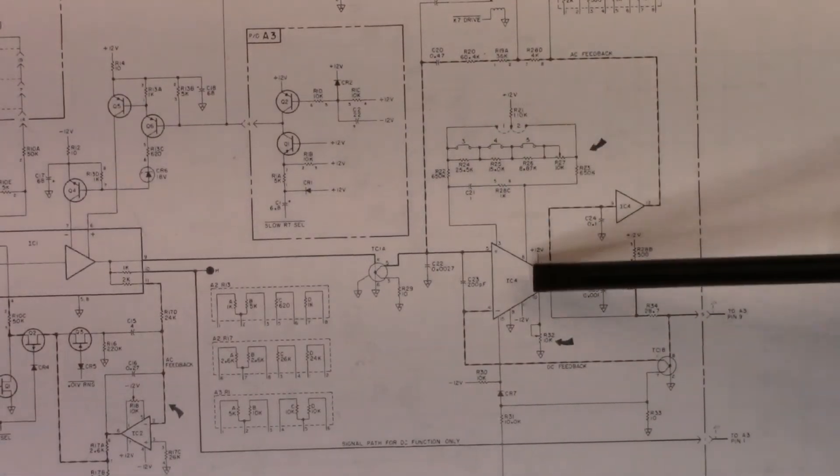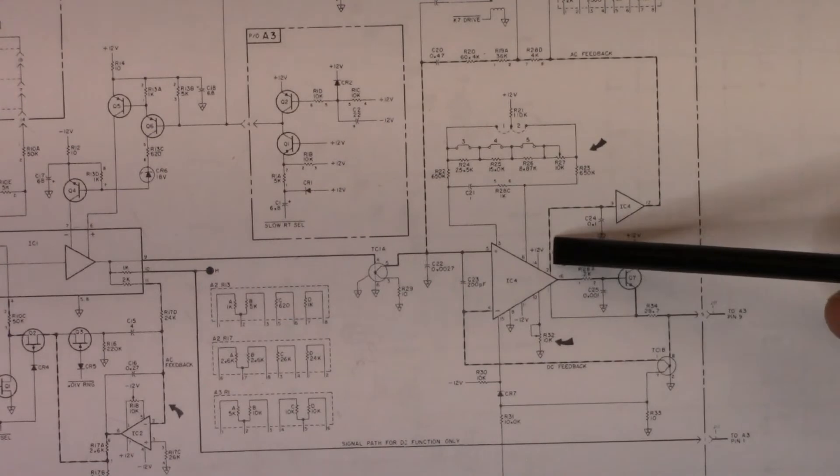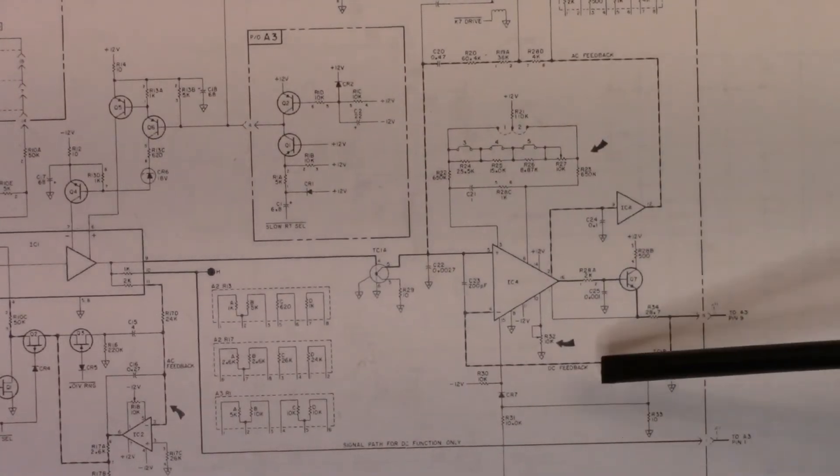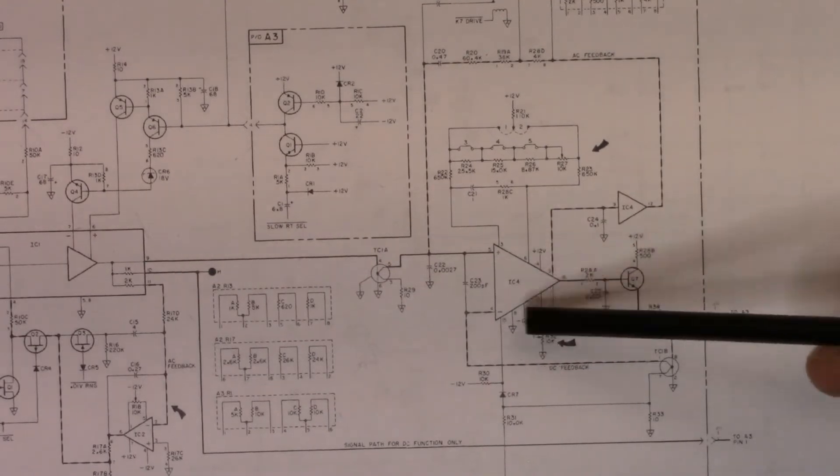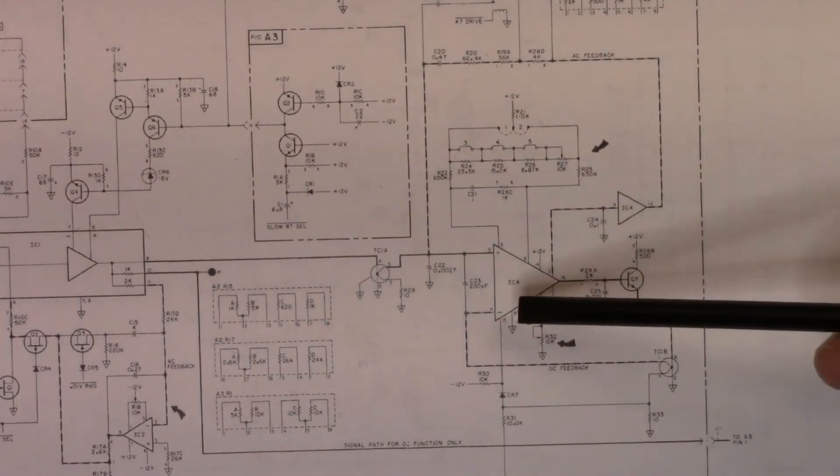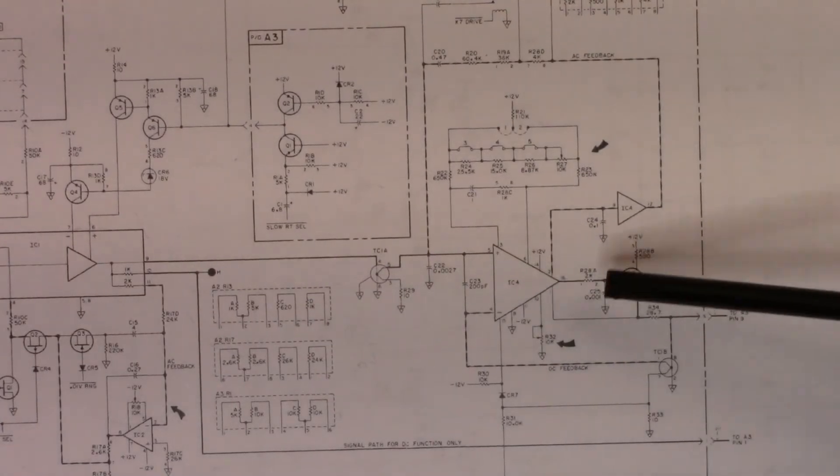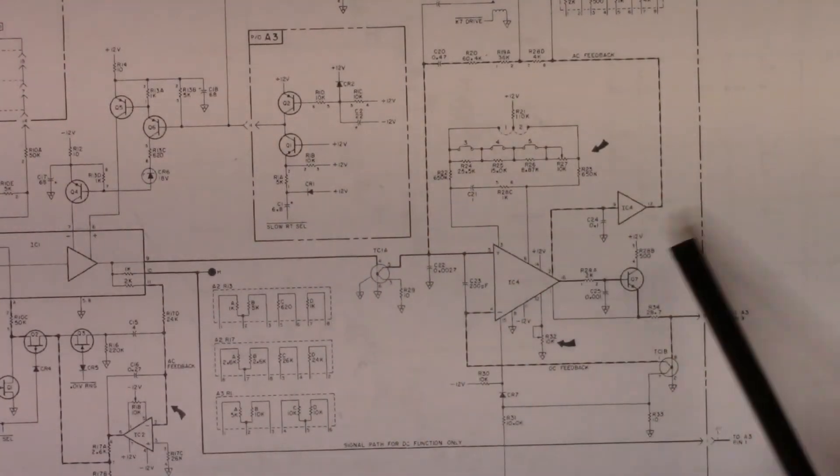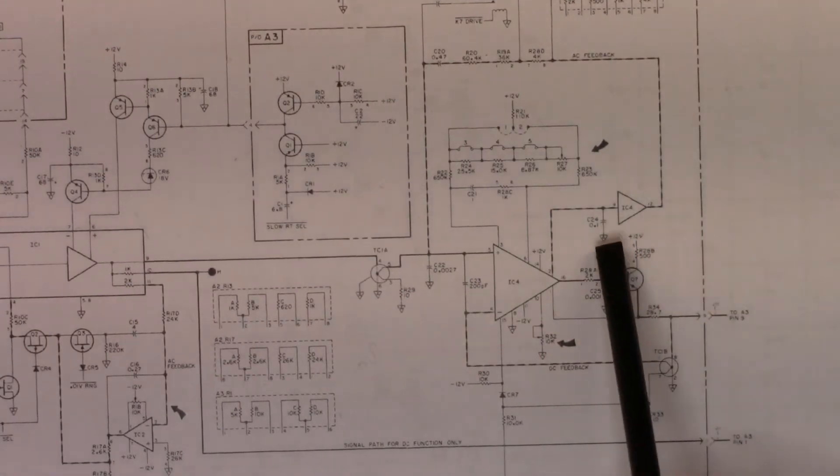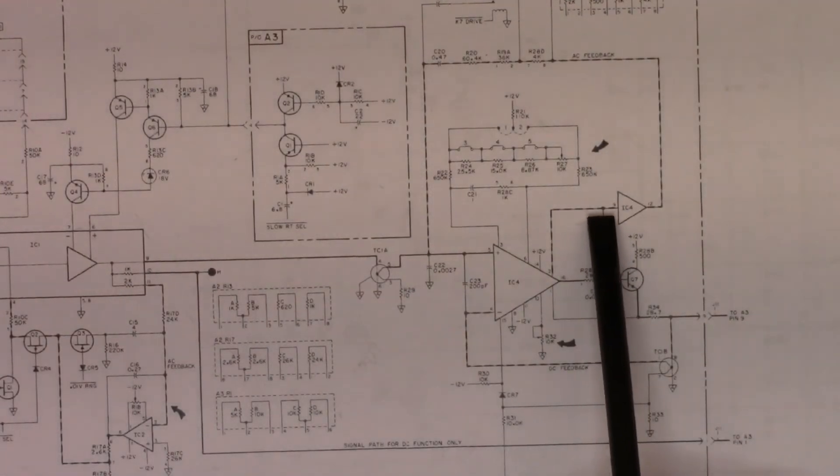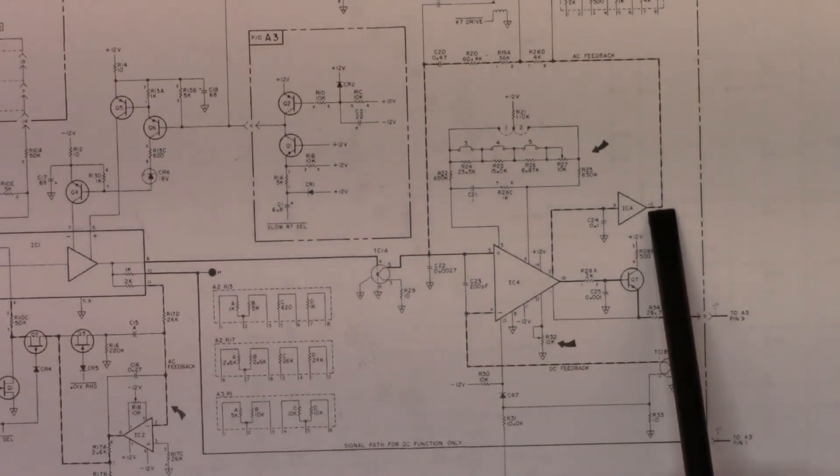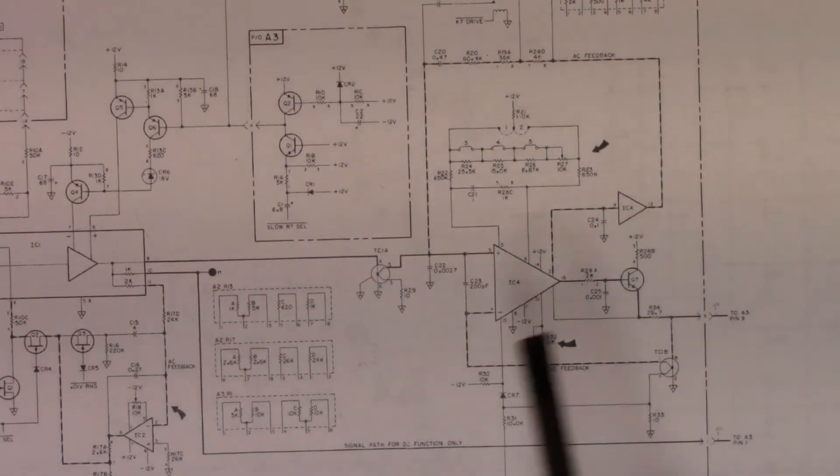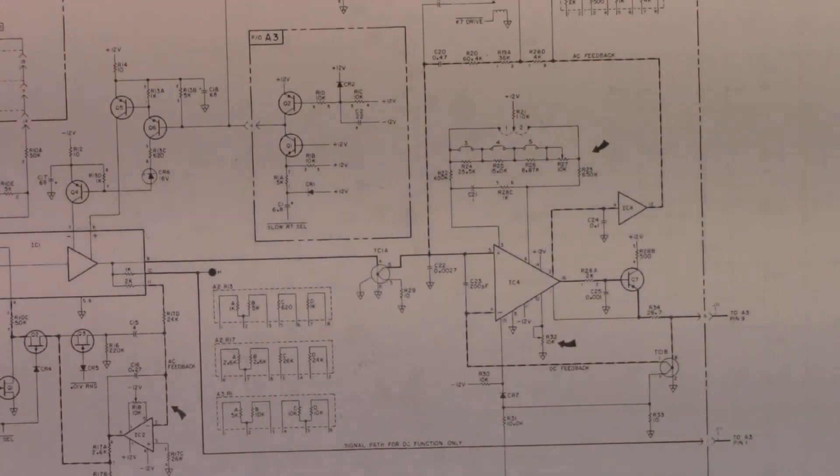It says it's an operational amplifier but it has offset values, it has balance values, this is the balance circuit for it. It's feeding out an AC feedback and a DC feedback path. Without having further information about what's going on I really don't know whether what is happening at this IC is actually correct. When it goes into an overvolt situation you do see a low voltage being put on pin 9 and that voltage being increased on pin 12, so this little amplifier here is doing its job.